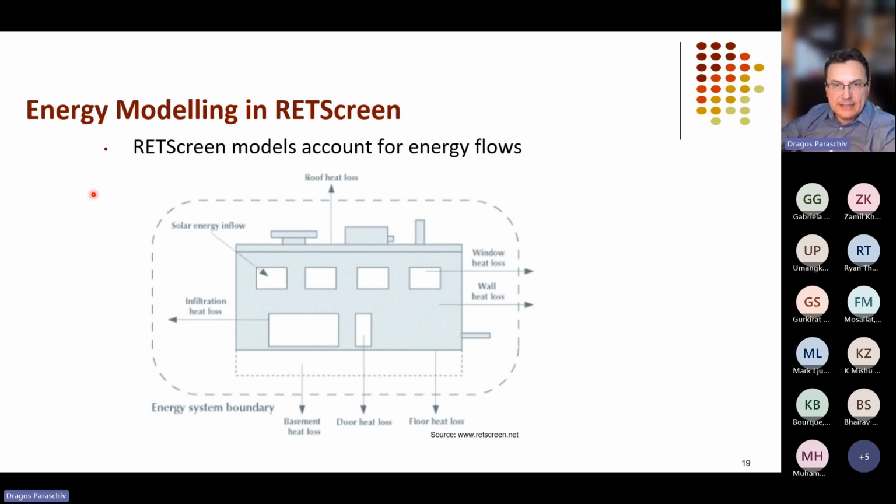I won't go into the details here, but I just want to point out the complexity of this model because it's important to be accurate in the inputs so that the calculation of these end uses is also accurate. So whatever takeoffs we get, the size of the windows, the R value of the walls, the infiltration rate, any of these parameters would have an impact on the calculation.